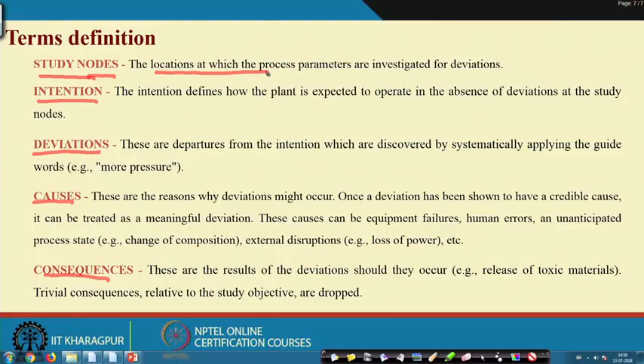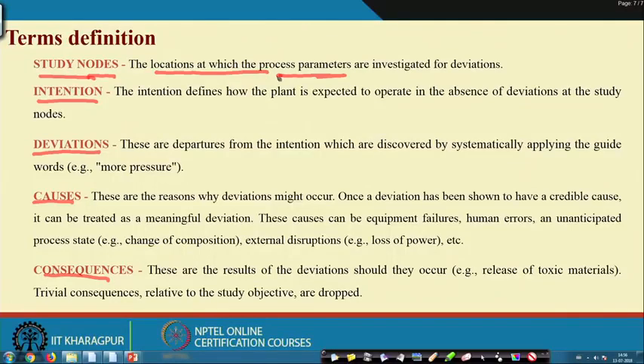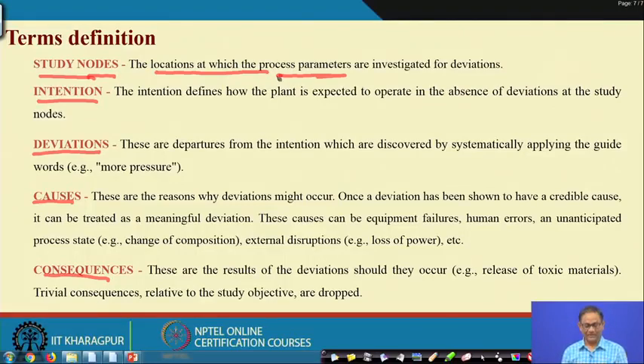For example, if we talk about the pressure tank system and we are interested to know the deviation in terms of pressure inside the tank, then the tank itself could be a study node, and the process parameter of interest is the pressure. If you think of the pump, then pump overrun is one deviation, and the time of running - too long or too short - is the parameter. Similarly, if you think of a chemical reaction, the reactor will be the location at which you conduct the HAZOP study and find out the deviations.